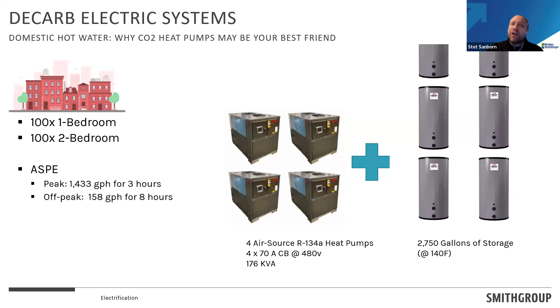And to Maria's point earlier, one of the big challenges, especially in retrofits, is trying to reduce our connected load so we don't impact upstream electrical infrastructure. So different heat pumps are going to have different connected loads, even though they can all supply that same performance that we're looking for. On the next slide, you'll see what going from a 134A machine to a CO2 heat pump does. These are commercial scale CO2 heat pumps meant for large scale domestic hot water systems. I can make the same amount of heat, but with far less equipment, because a CO2 heat pump performs very well at low outside air temperatures, and it loves making really hot water.